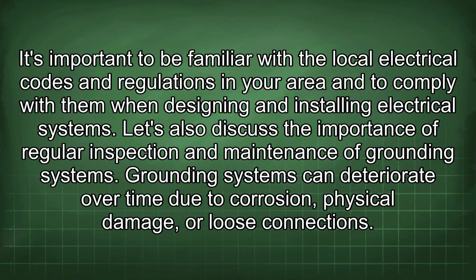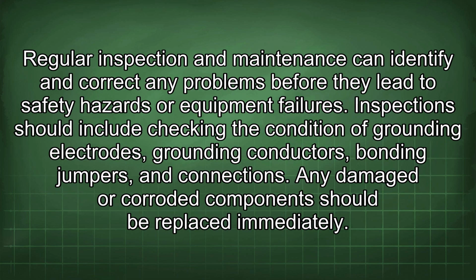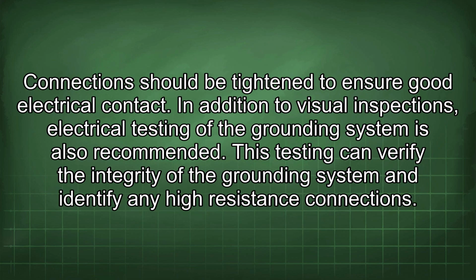Let's also discuss the importance of regular inspection and maintenance of grounding systems. Grounding systems can deteriorate over time due to corrosion, physical damage, or loose connections. Regular inspection and maintenance can identify and correct any problems before they lead to safety hazards or equipment failures. Inspection should include checking the condition of grounding electrodes, grounding conductors, bonding jumpers, and connections. Any damaged or corroded component should be replaced immediately. Connections should be tightened to ensure good electrical contact.